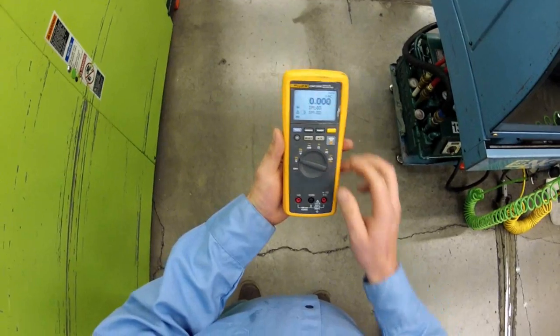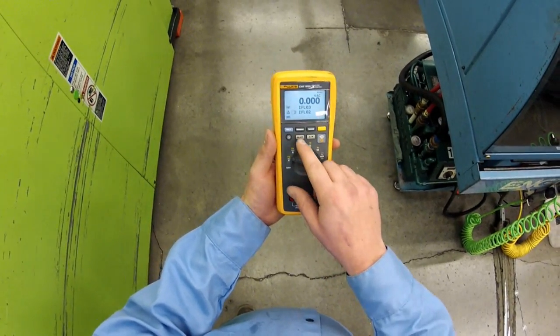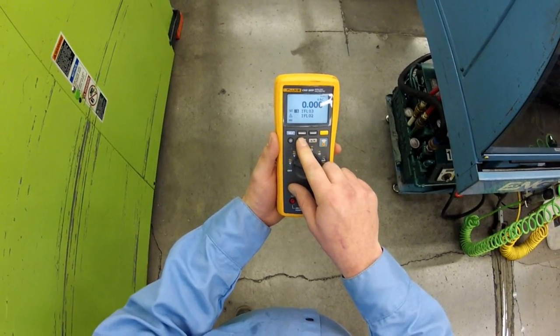Now that we've connected with our two iFlex wireless modules, we're going to select both of the modules. We're going to hold the up and down button and we can see that both of our heating elements are currently pulling 9.5 and 9.6 amps.